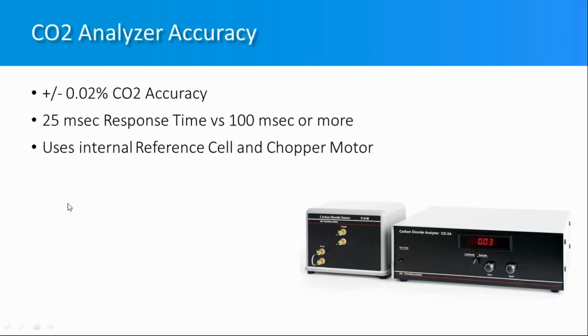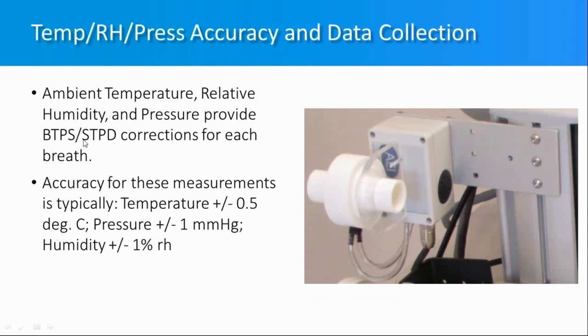For the rest of the system, the same high tolerances apply to all parameters used to correct flow and the gas sample in terms of STPD. The pneumotach measures flow, and the compensating electronics box contains all the sensors — temperature, relative humidity, and pressure — built in.